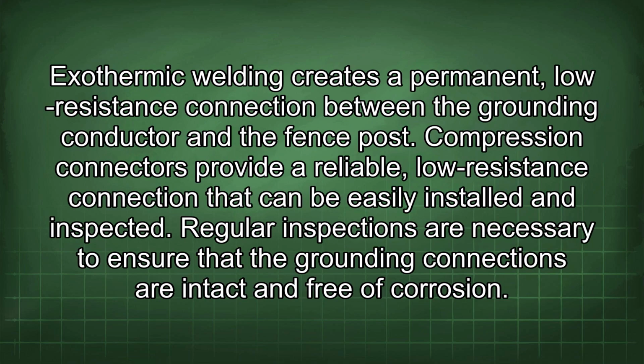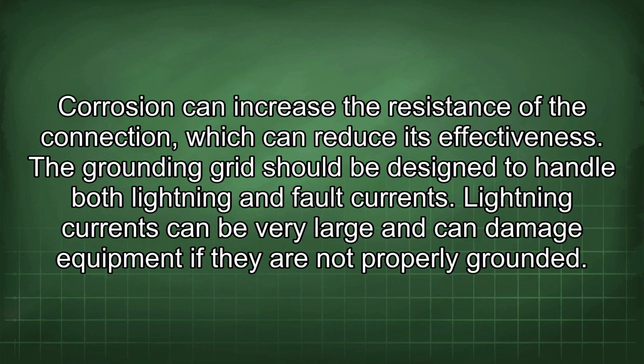Exothermic welding creates a permanent, low-resistance connection between the grounding conductor and the fence post. Compression connectors provide a reliable, low-resistance connection that can be easily installed and inspected. Regular inspections are necessary to ensure that the grounding connections are intact and free of corrosion. Corrosion can increase the resistance of the connection, which can reduce its effectiveness.